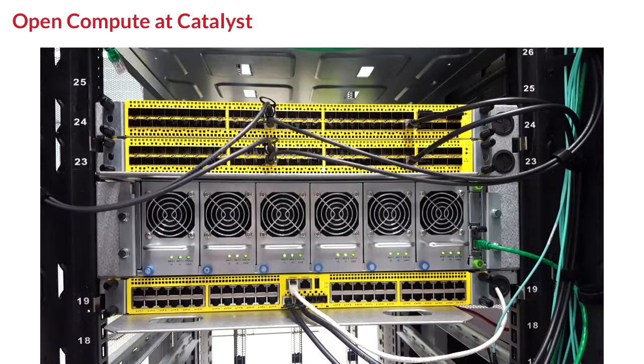That's our power shelf and our beautiful Cumulus Linux switches from Penguin Computing. Love the yellow. Those are actually 12 volt switches, so they're running off the rails as well. Penguin Computing have only just made those available when we decided to buy them. The power cables on the back are custom made couplings to go onto the 12 volt rails. That's new. In this power shelf, there are 6 PSUs. There are 2 3-phase circuits running in the back of it, and it's N plus N redundant. It's not quite grunty enough to power the entire rack when it's full, but it's still pretty good.